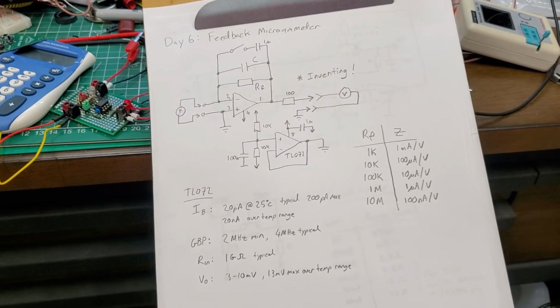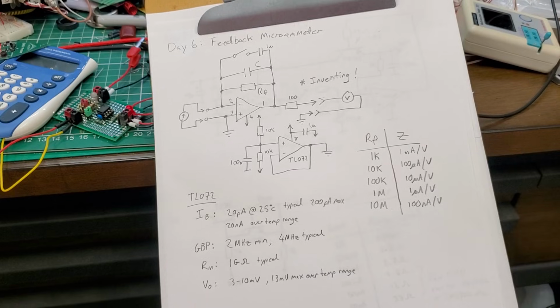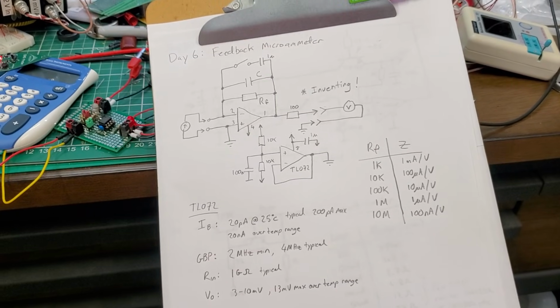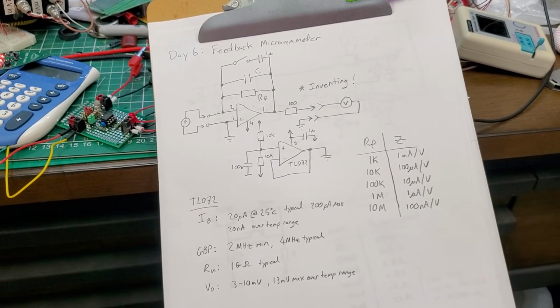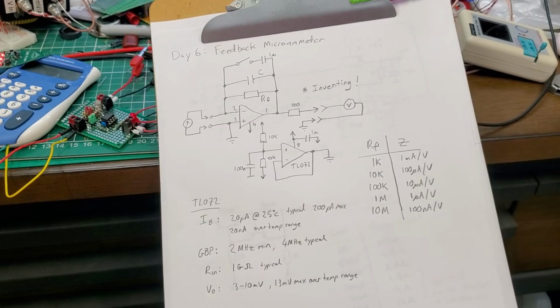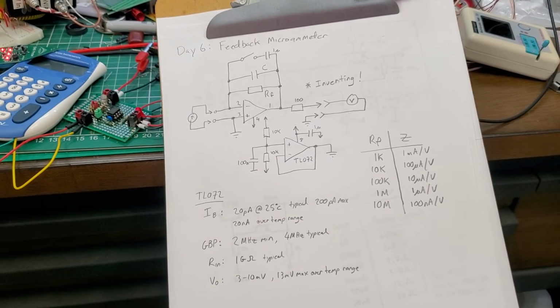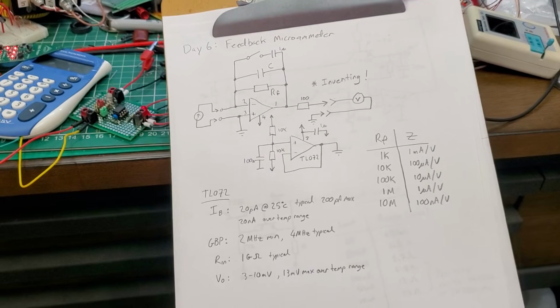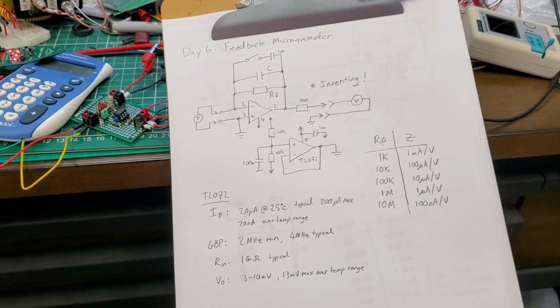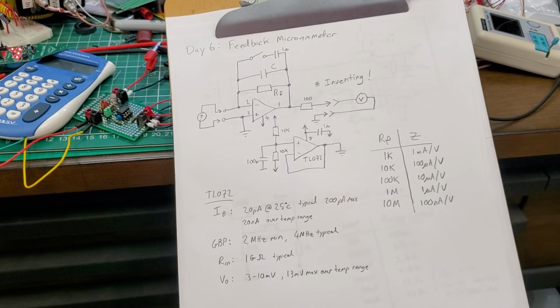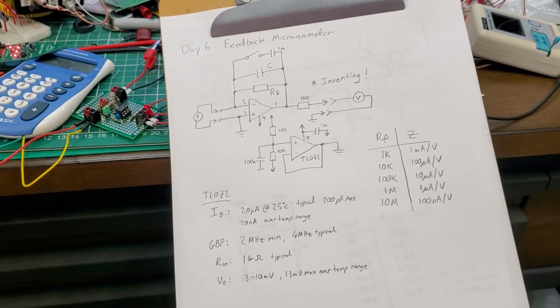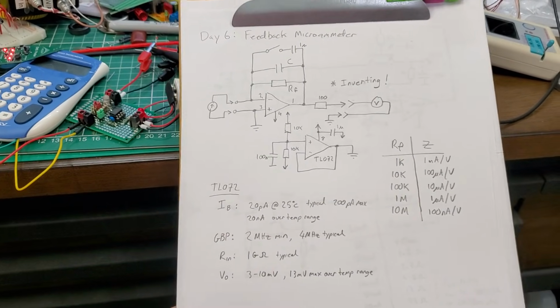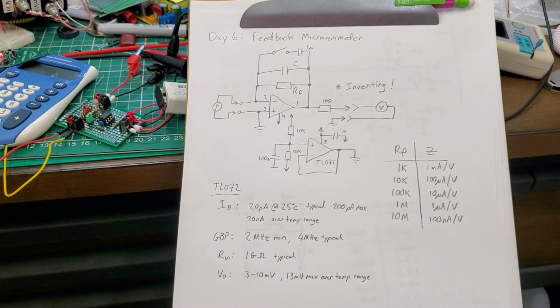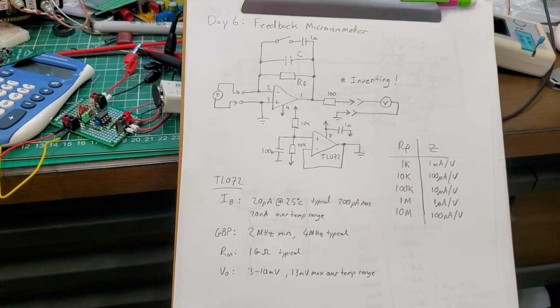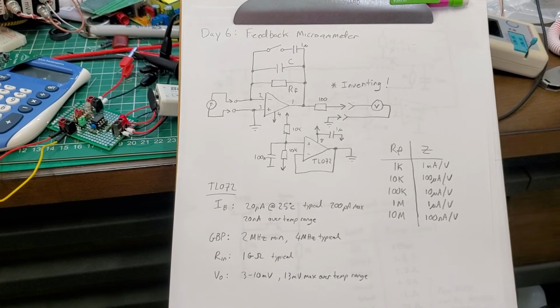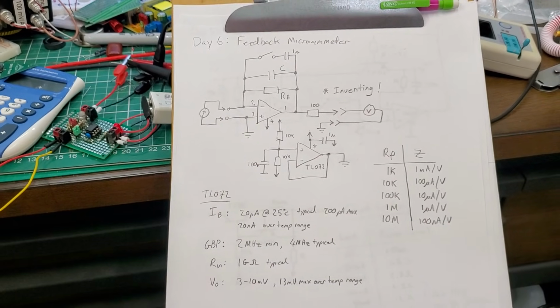You can also use the magnetic field that a current produces. That's used in clamp-on meters. DC clamp-on meters generally have a Hall sensor, and they need some mechanism of zeroing because they're not induction based, whereas an AC one would be based on a little transformer, essentially a current transformer. But in DC, for measuring very small currents, the magnetic field produced is actually quite tiny, so that's not terribly practical for microamps and below.